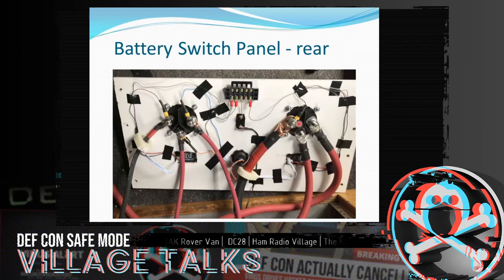Here's the back of that same panel. You can see how large some of these cables are. This is a quad zero gauge wire—very big, very expensive, and really hard to work with, as you might imagine. These are two double zero cables that go to each battery; this is the 200 amp side of the circuit, and this is the 80 amp side of the circuit, using 4 gauge wire for that wiring.